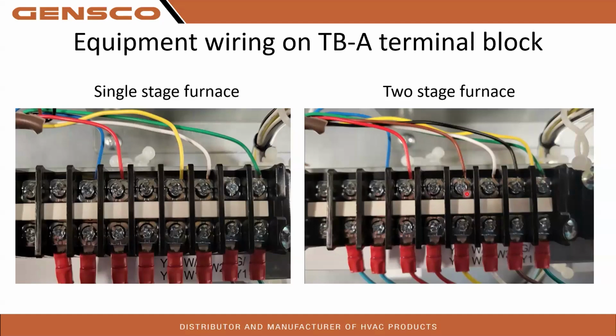In our application, it just means that we're turning the fan on. Whether you're running the heat pump in heat or cool, it is going to be energizing the Y terminals. It's not going to energize W, because W will kick on the gas heat. We don't want that.